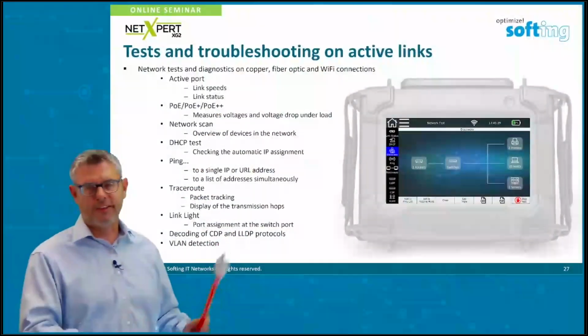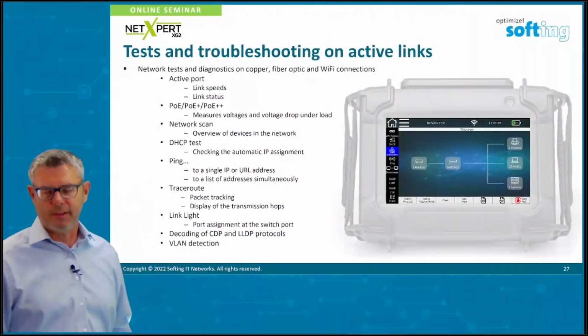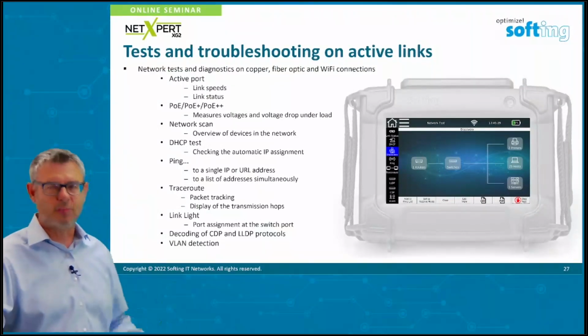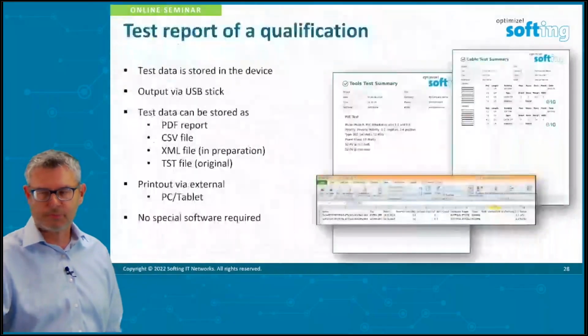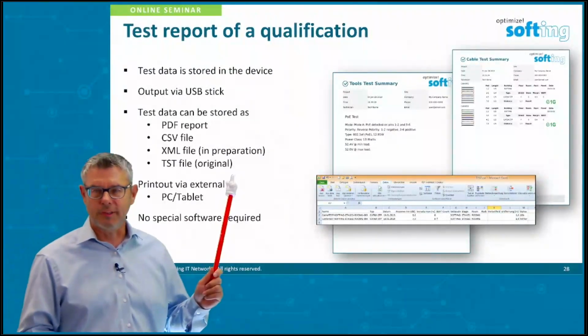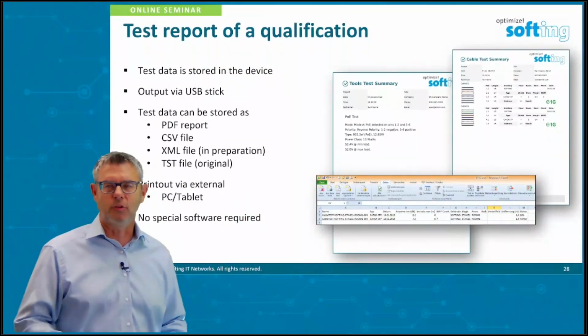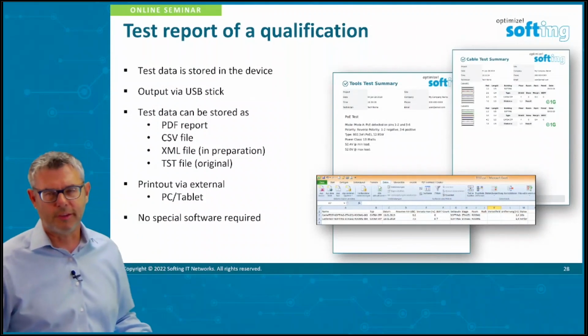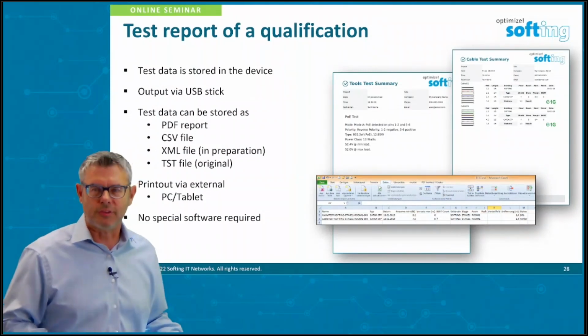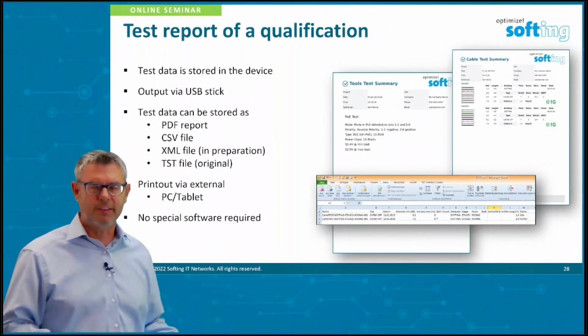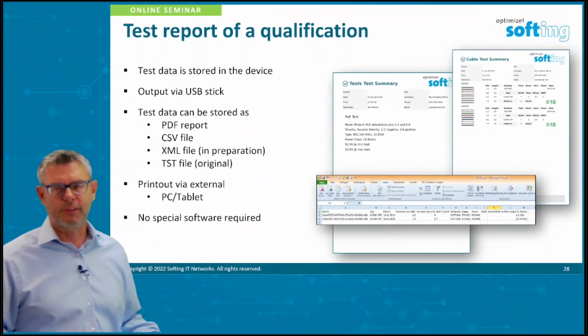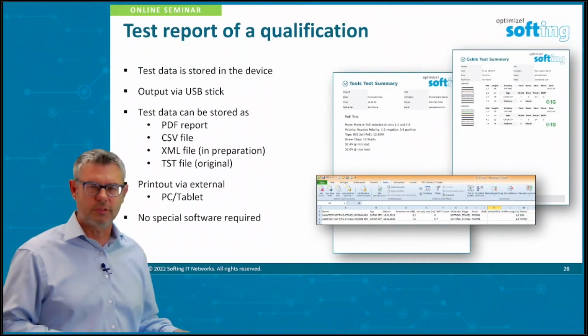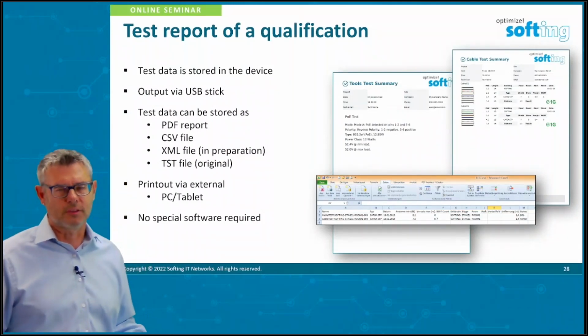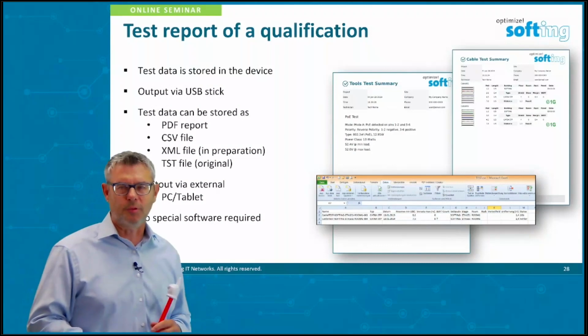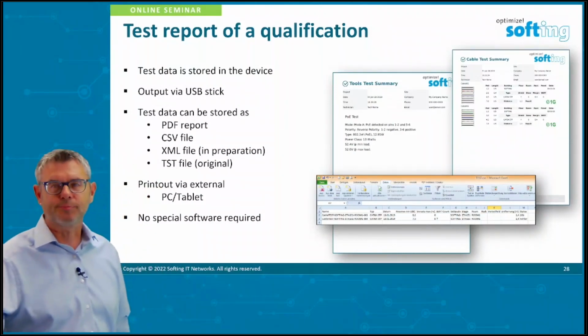Also, again, active testing - as we saw earlier, when we start up a network, we start up the active part. And now it comes to documentation. A good qualifier can give you documentation on the qualification runs it did, which is a valid documentation of an installation, especially for smaller applications or installations. That's a proper way to document an installation.